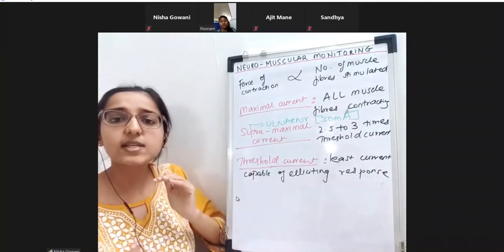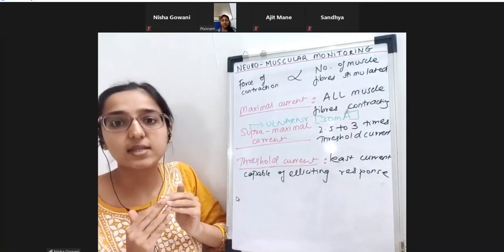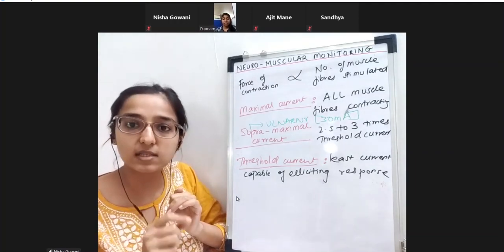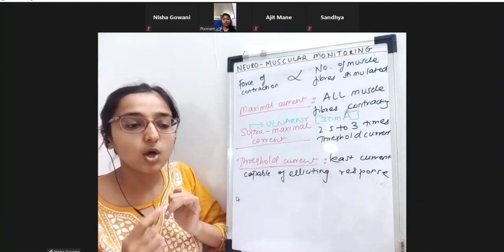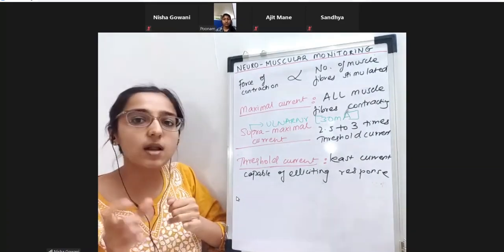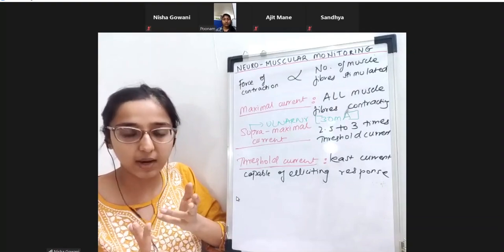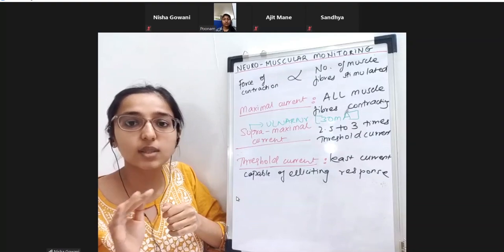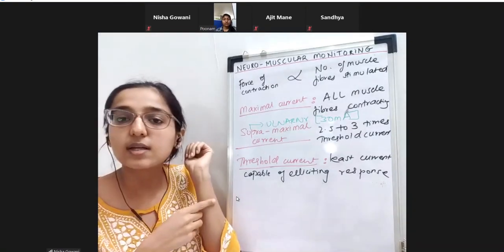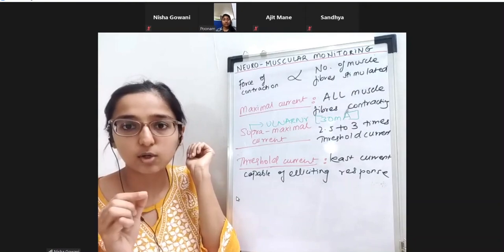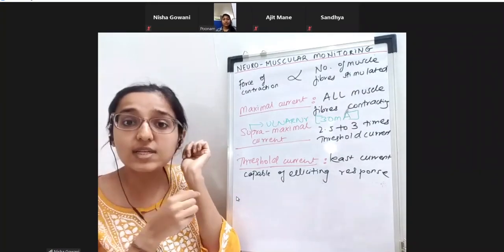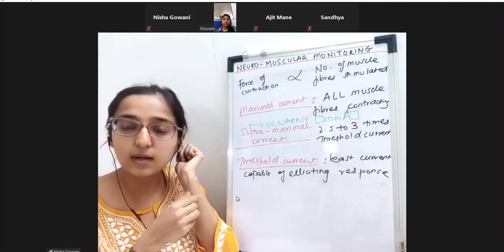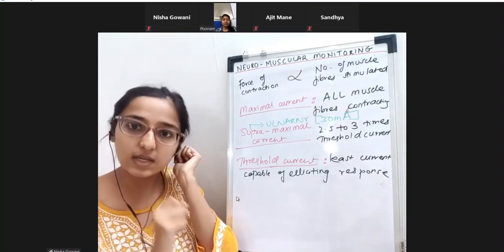Sometimes supra-maximal will be a lesser value - it is not a fixed number. We always estimate supra-maximal before starting a case. When we use needle electrodes instead of surface gel-based electrodes, the electrode is very close to the nerve, so the current requirement will be less.